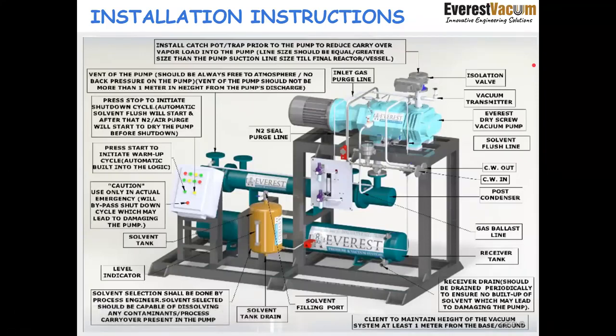Another important thing is that solvent selection is very critical. We should select a solvent for flushing purposes that is capable of dissolving the contaminants or process carryover entering into the pump. So these are the basic installation instructions, how the setup should be followed and how it looks.